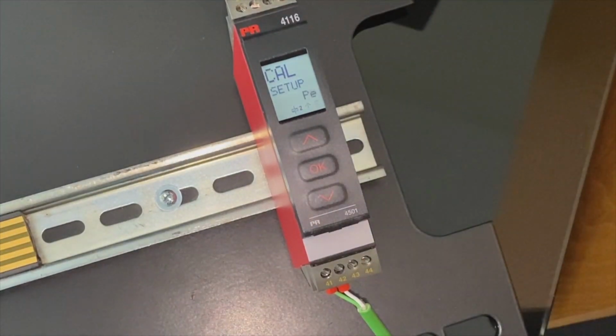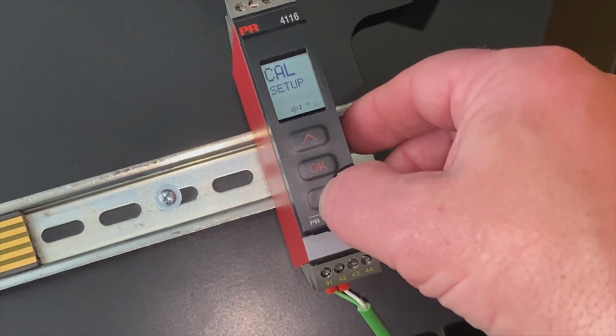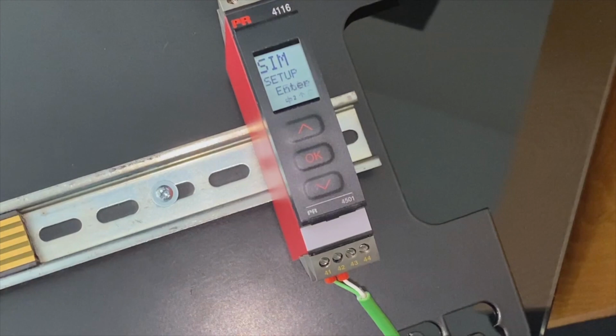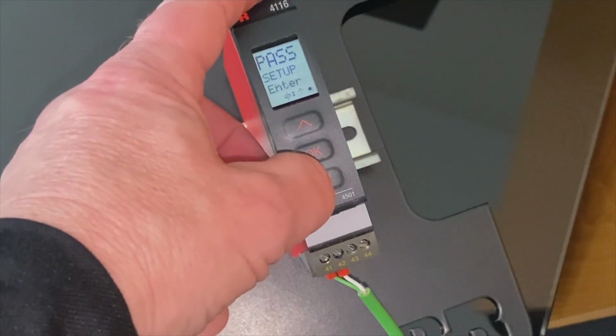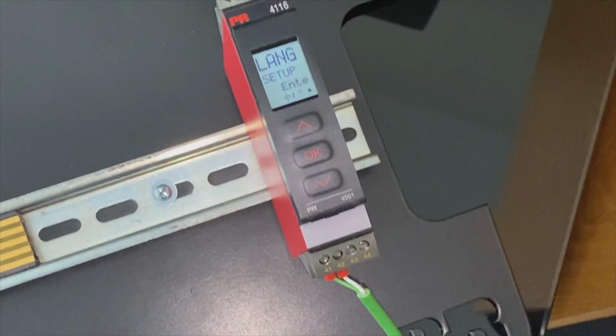Our next choice is calibration. You can do a single or a 2-point calibration on anything that you're working with. Maybe you have a level system out there, you see a translucent tank, you can tell that it hasn't been calibrated for 30 years, and you can tell the device what the actual value, the real value is, and simply do calibration. There's a simulation mode, which will enable you to test the system to see if it's working the way you've programmed it prior to commissioning it. There is password protection, as well as 7 different languages, and as a safety, latching is available as well.